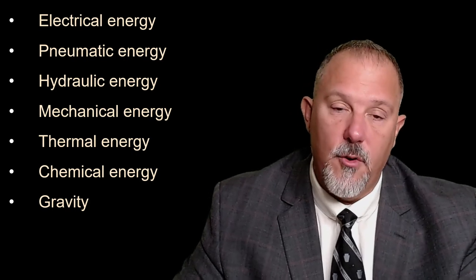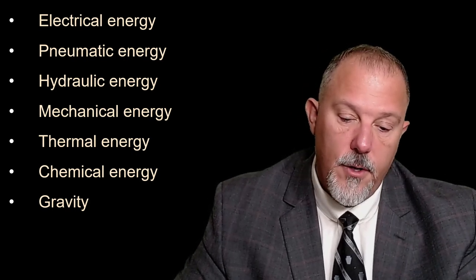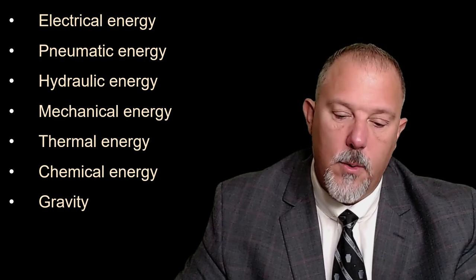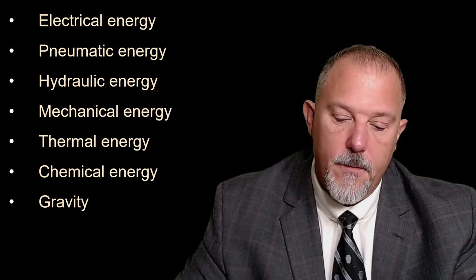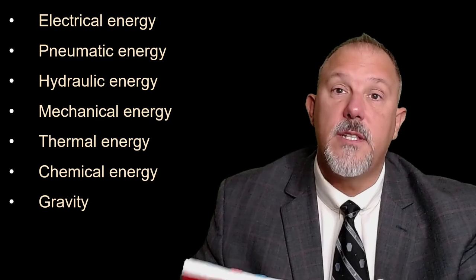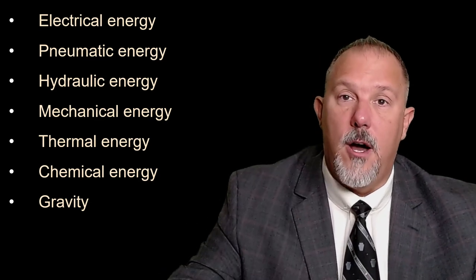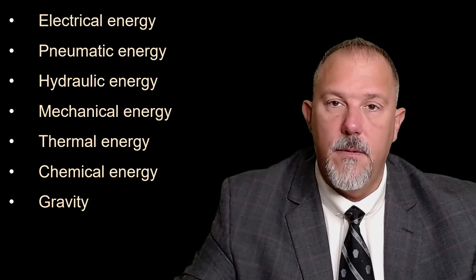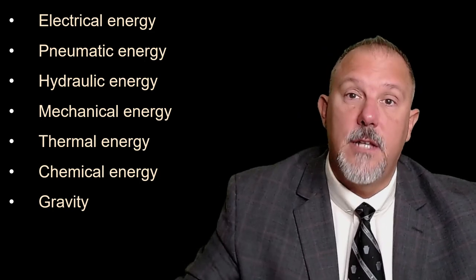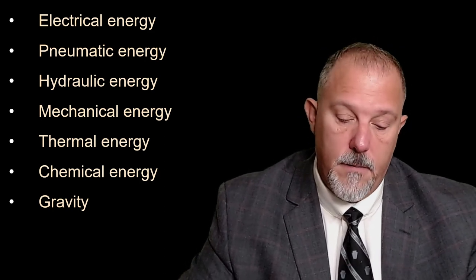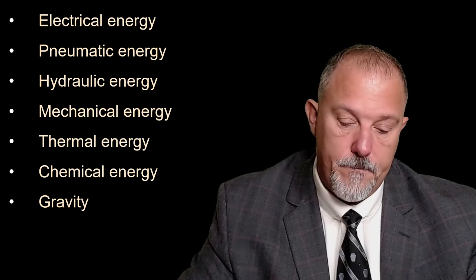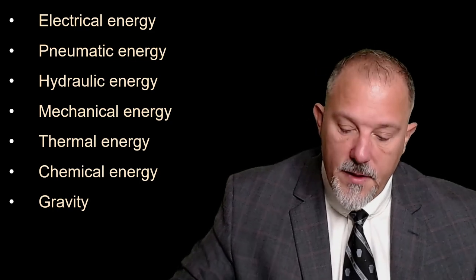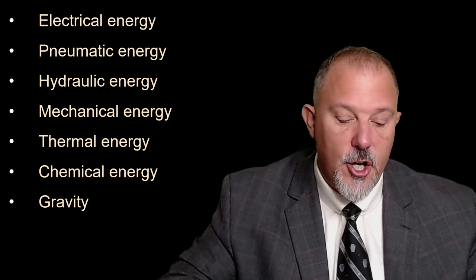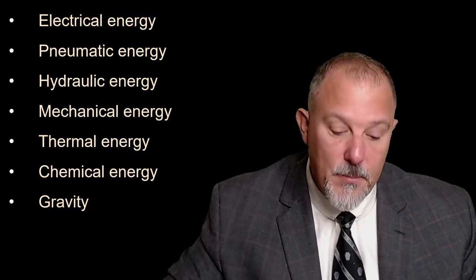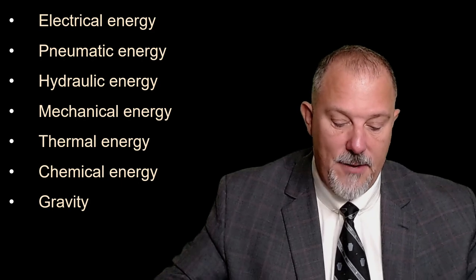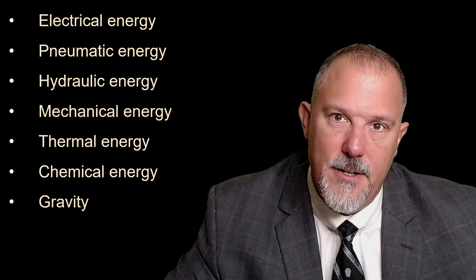Understanding that you need to have all of your employees involved. You have to have proper interlocks. You have to have coordination of your lockout tagout procedures, because in some cases you have to apply one lock first before another lock. The process that you take might be important. You have all the equipment that you're allowed to use. You have complex and simple lockout tagout procedures. And remember, this is just a recipe.